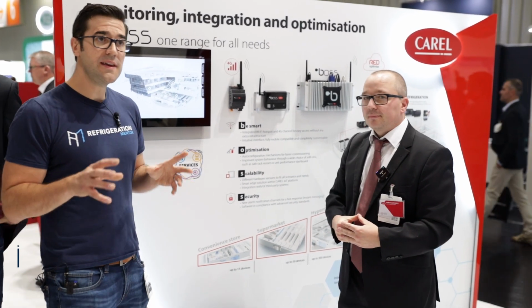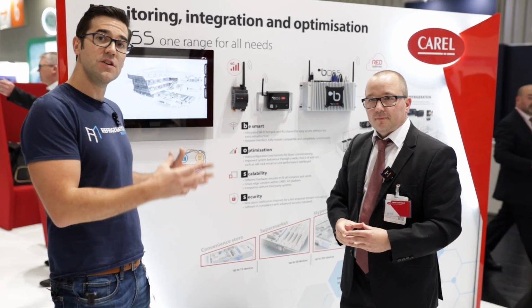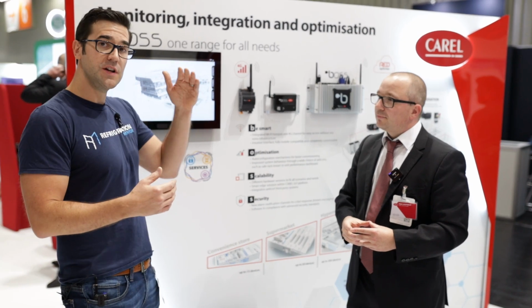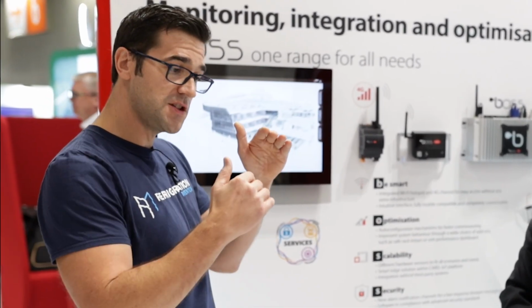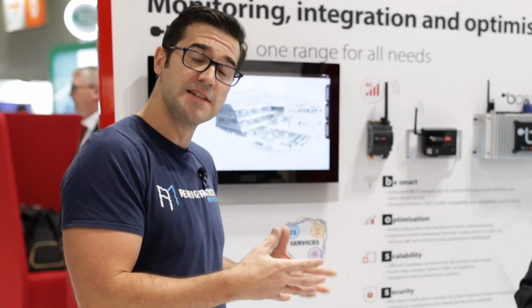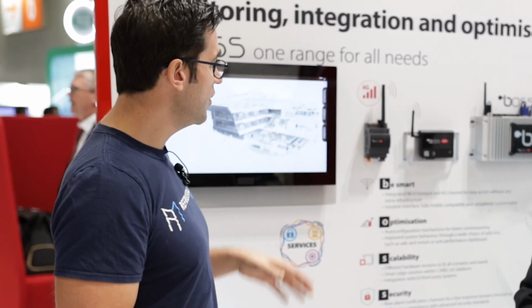And this is what's really key to understanding controllers, because this is what they're all about. Saving energy for your customers, making your systems more efficient. So as he talked about, reducing that head pressure, increasing the suction pressure, reducing the compression ratio or the pressure ratio of that compressor of that system makes it more efficient. It's really cool to see.